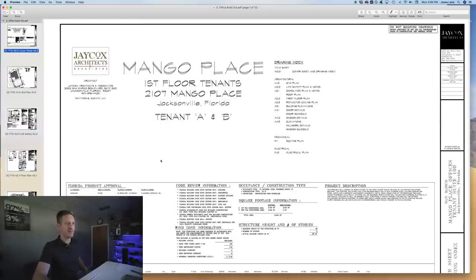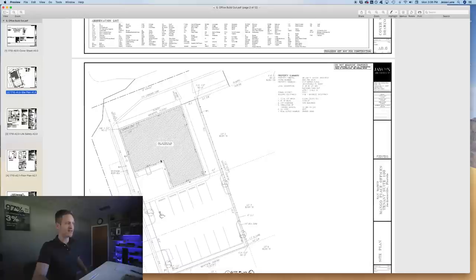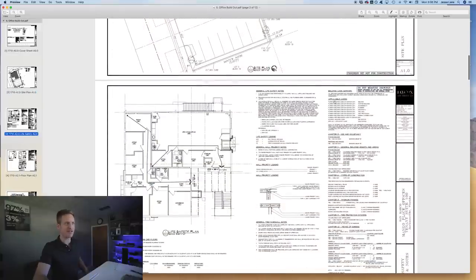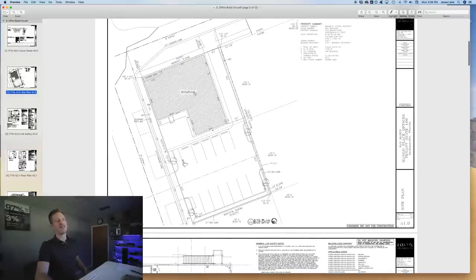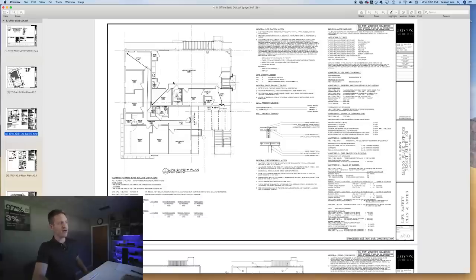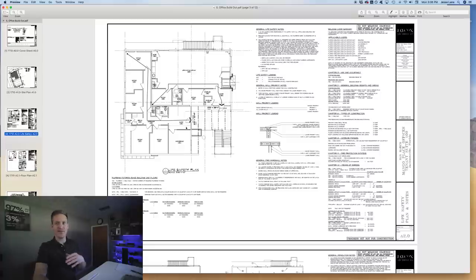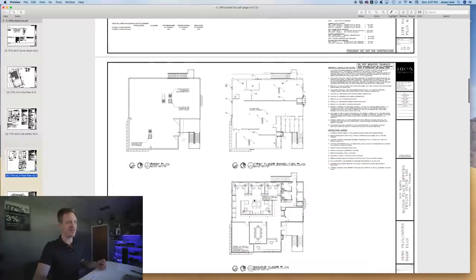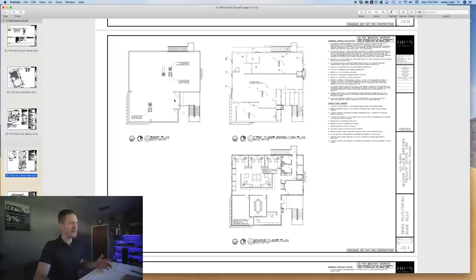Here's a good-sized office build-out. The first page has the wind zone info, building code summary, general life safety notes, and a site plan showing the work area on the lot. The life safety plan shows egress travel lines. We actually ran into an issue on this project: the hallway needed an extra five feet because it was 20-foot max for egress, so the fire marshal had comments and we had to readjust the floor plan.